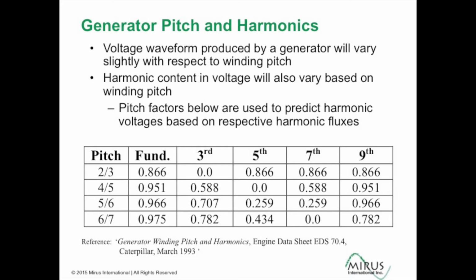However, we've got a higher fraction of fifth and seventh and ninth harmonics. So this generator would produce lower levels of third harmonic voltage distortion than, say, the 4/5 or the 5/6 generators, which have a higher pitch factor. So it's worth noting that in theory the 2/3 pitch generator should not produce any third harmonic voltage, but will produce more fifth and seventh.